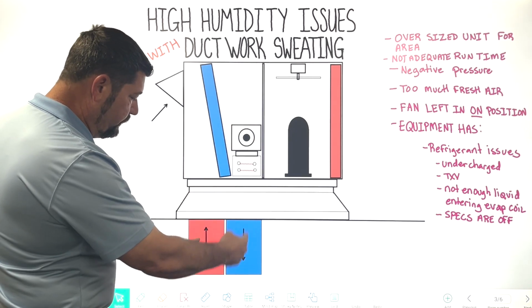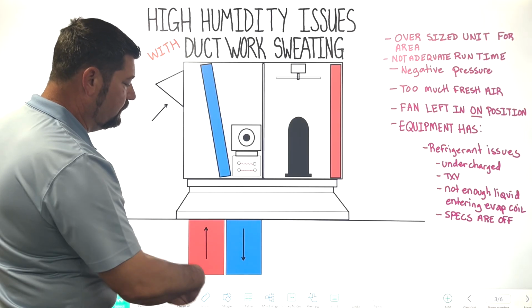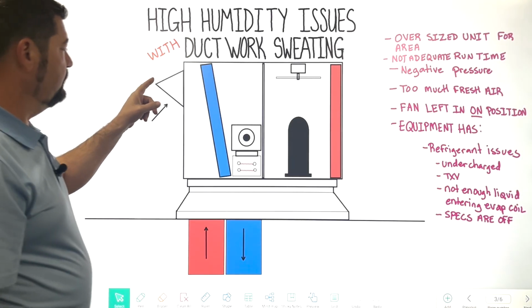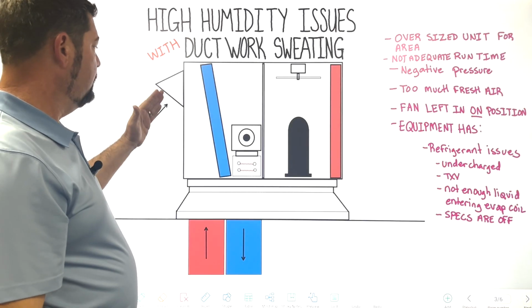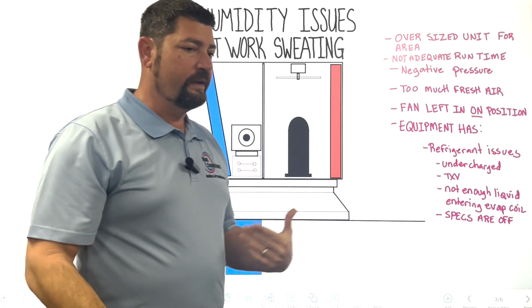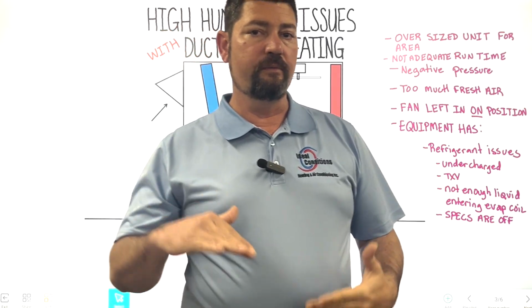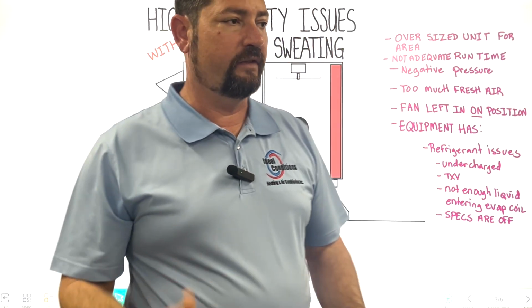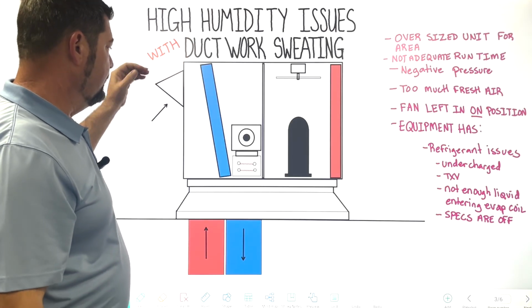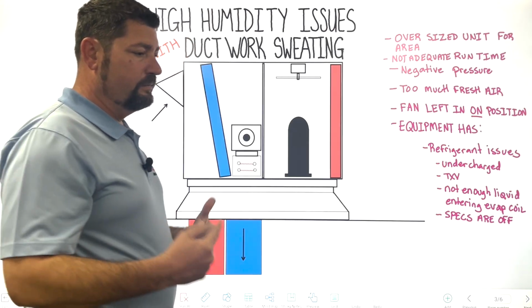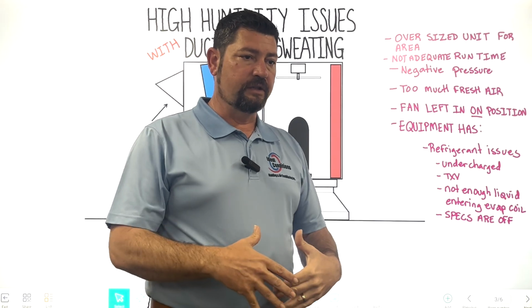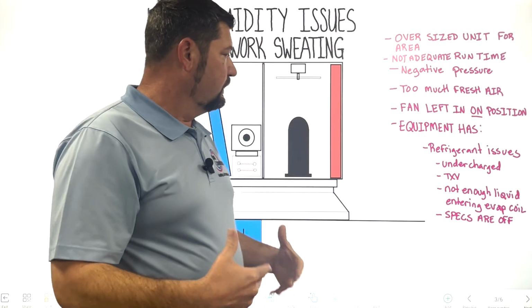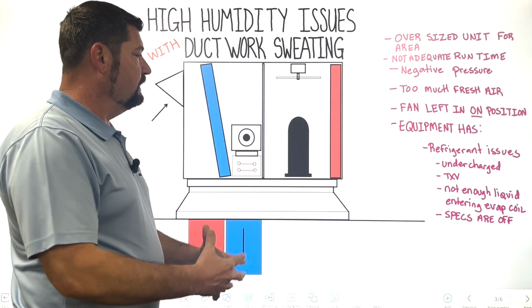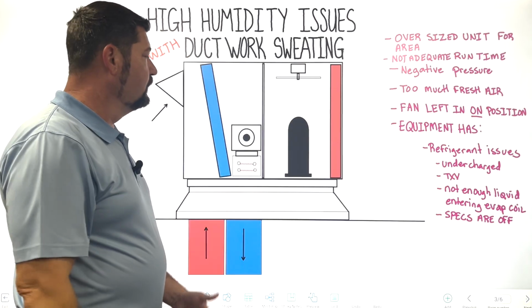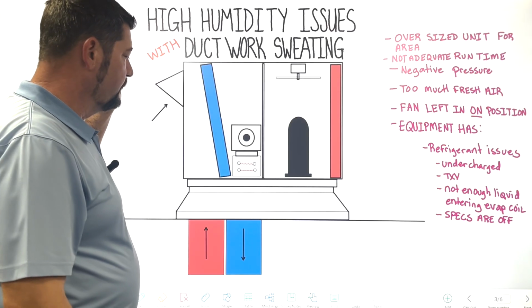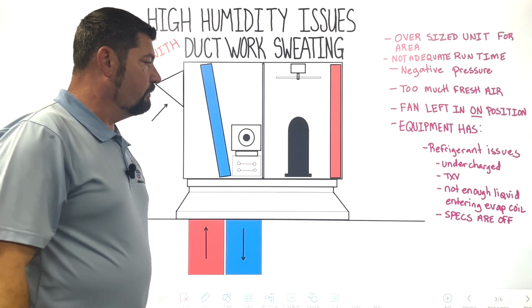So now you're going to be putting a higher humidity back into it, so that humidity is really not going anywhere. So sometimes these fresh airs are open too much, and you need to close them off. Depending on what region you're in, if you're up north and humidity's low, you want to take advantage of some free AC. If it's not an economizer that can regulate and it's just a manual damper, you're going to have to understand your customer, understand the equipment, understand the lay of the land, being the space that you're conditioning, and what their concerns are, so you can adjust the mechanical system to balance their requirements.